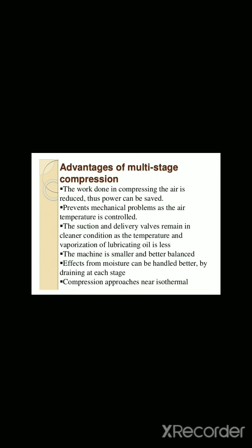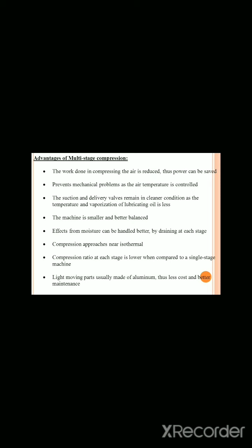Advantages of multi-stage compression: the work done in compressing the air is reduced, so power can be saved. Again, it prevents mechanical problems as the air temperature is controlled. Next, the suction and delivery valves remain in cleaner condition as the temperature and vaporization of lubricating oil is less. Next, the machine is smaller and better balanced. Next advantage is effects from moisture can be handled better by draining at each stage. Next, compression approaches near isothermal. Next one is compression ratio at each stage is lower when compared to a single stage machine. Next advantage is light moving parts, usually made of aluminum, thus less cost and better maintenance.